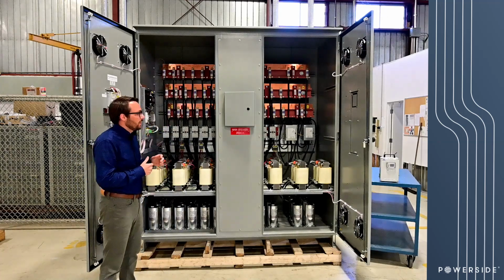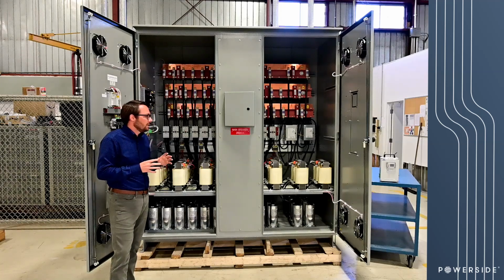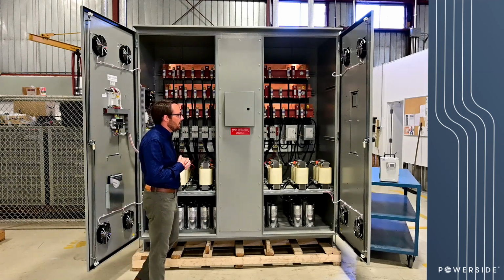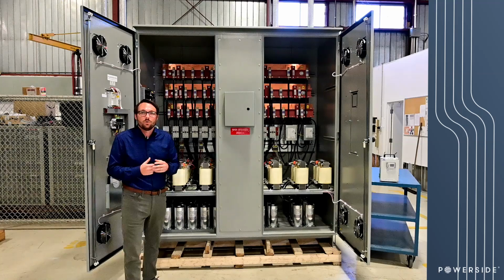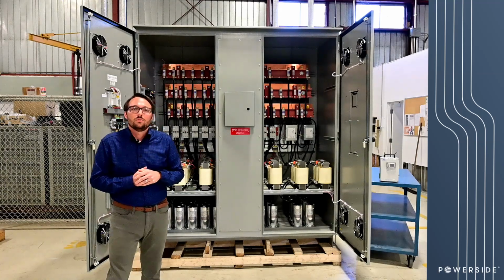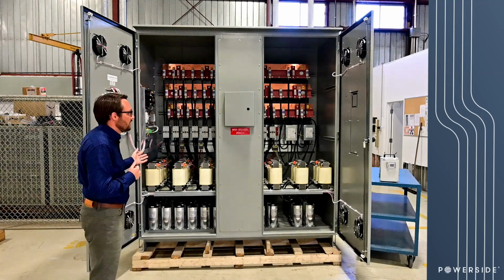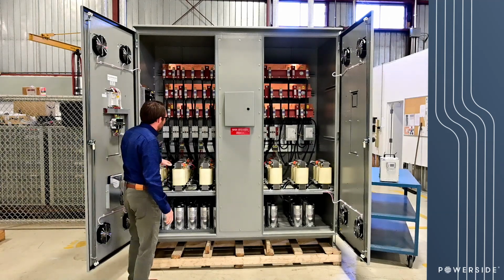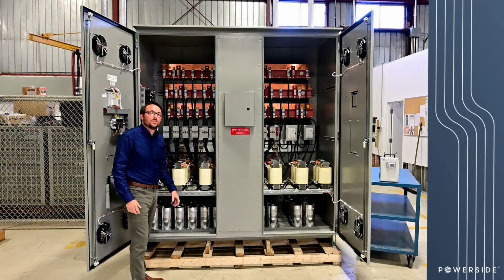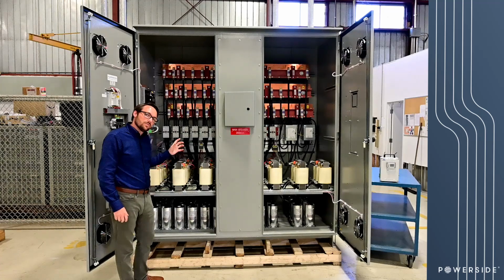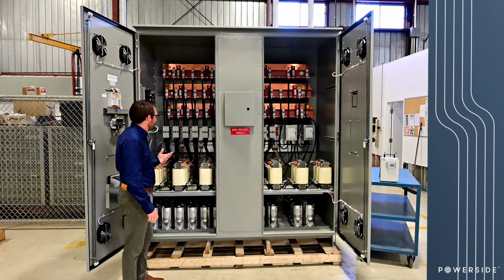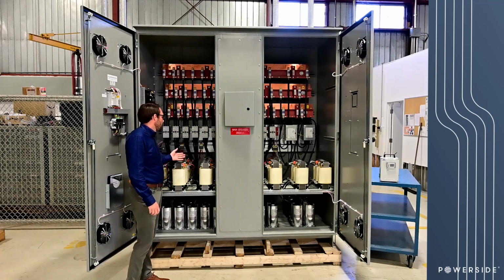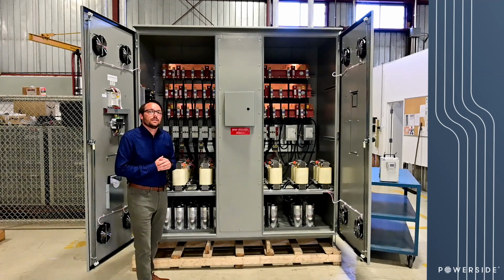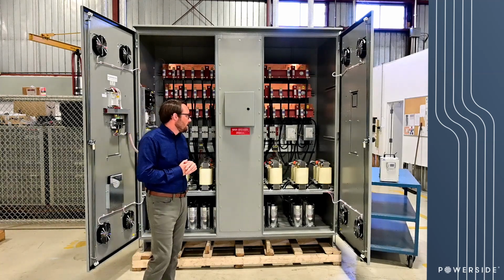Now, luckily for this application, the harmonics weren't extremely high. However, they were enough where we certainly needed to use detuning reactors in this case. So these reactors help prevent these capacitors from being a low impedance source for harmonics, and they also prevent the capacitors from amplifying harmonic content on the system.